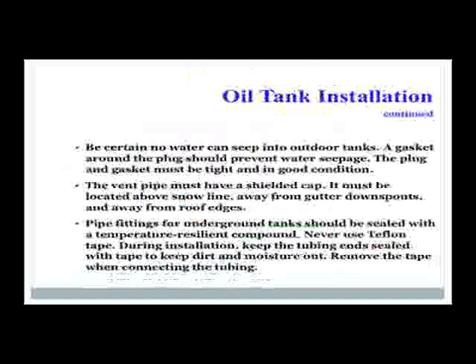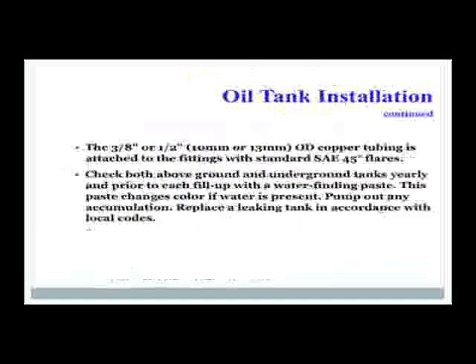Be certain no water can seep into outdoor tanks. A gasket around the plug should prevent water seepage. The plug and gasket must be tight and in good condition. The vent pipe must have a shielded cap. It must be located above snow lines, away from gutters and downspouts, and away from roof edges. Pipe fittings for underground tanks should be sealed with temperature-resistant compounds. Never use Teflon tape. During installation, keep the tubing ends sealed with tape to keep the dirt and moisture out. Remove the tape when connecting the tubing. The 3/8 and 1/2 inch copper tubing is attached to fitting with standard SAE 45-degree flares.